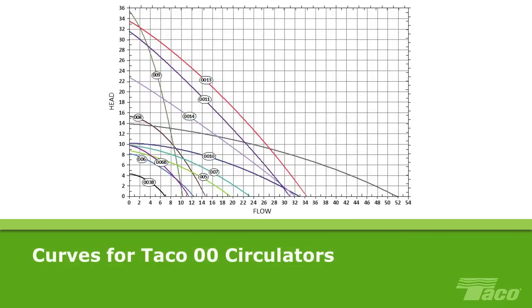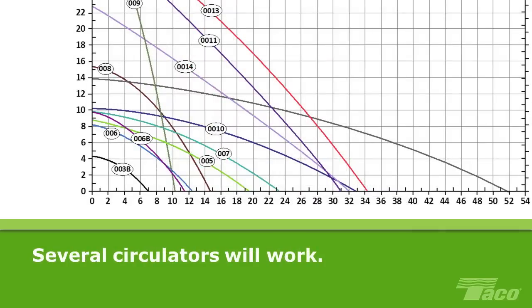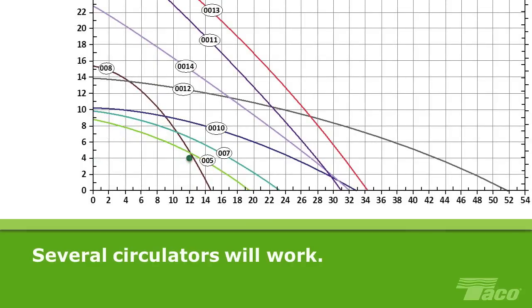Here's a graph showing the curves for the various models of Taco 00 circulators. Using our same example of a system that requires 12 gallons per minute flow at 4 feet of head, we can see that several models of circulators will meet those requirements: the 0010, the 0011, the 0012, and the 0013 too.